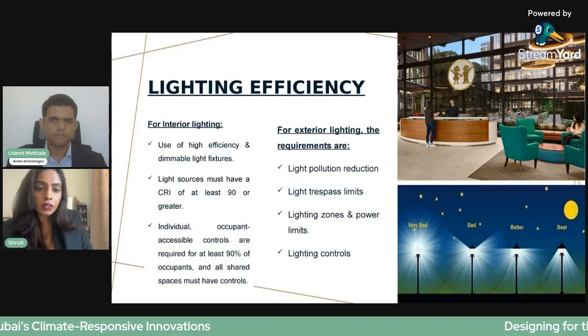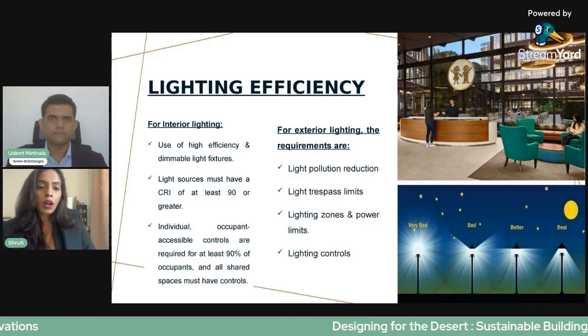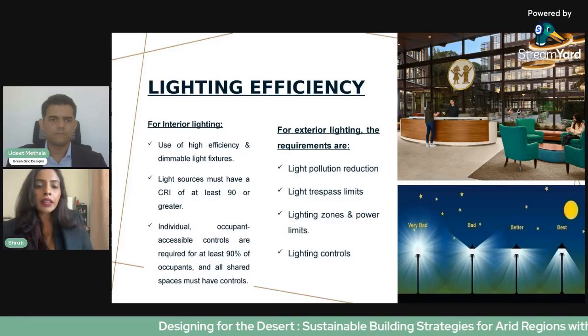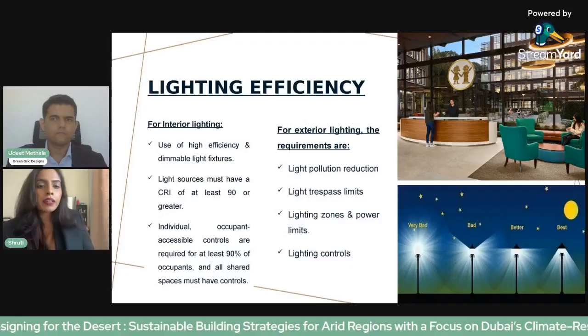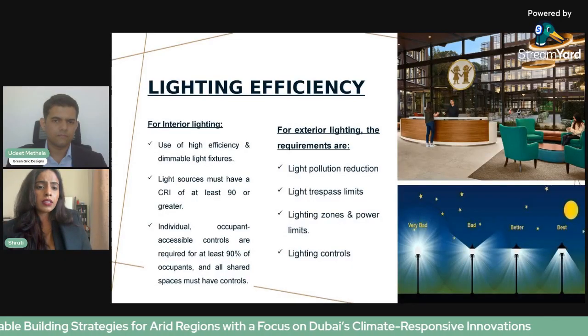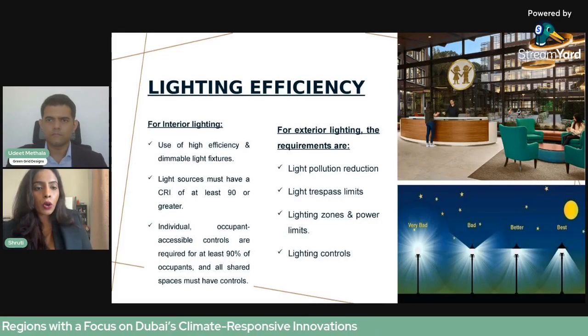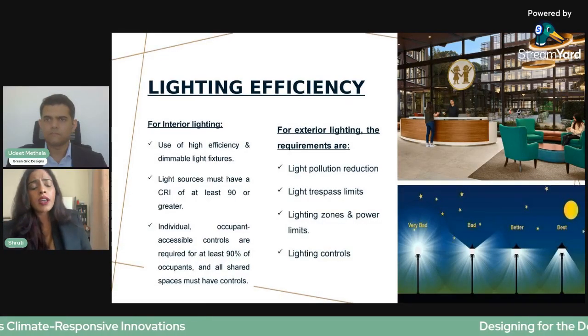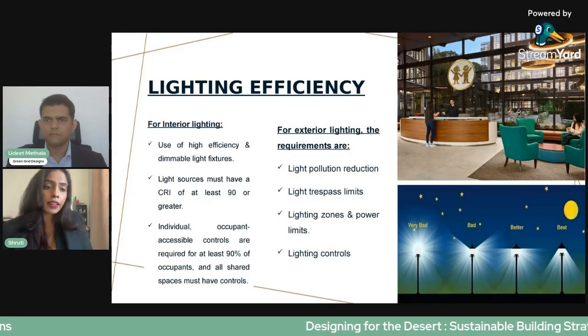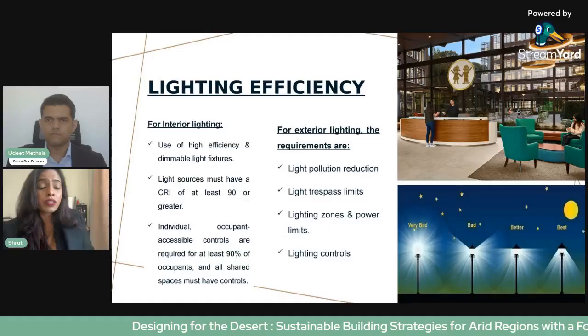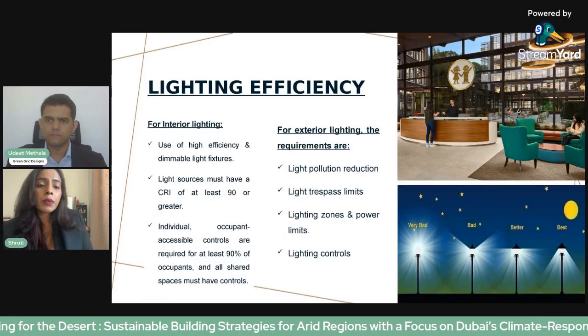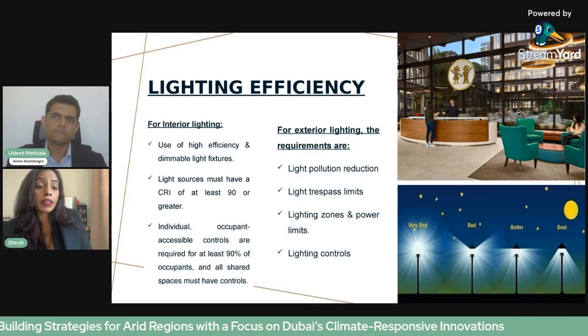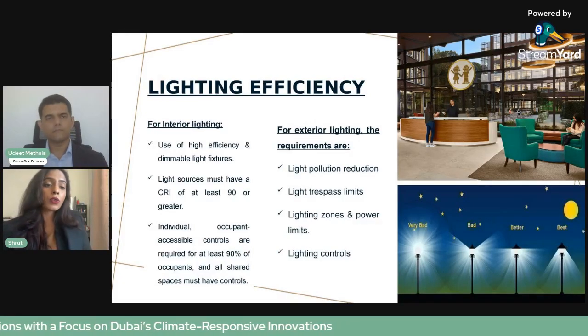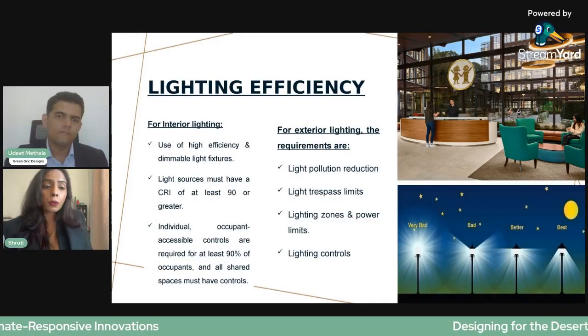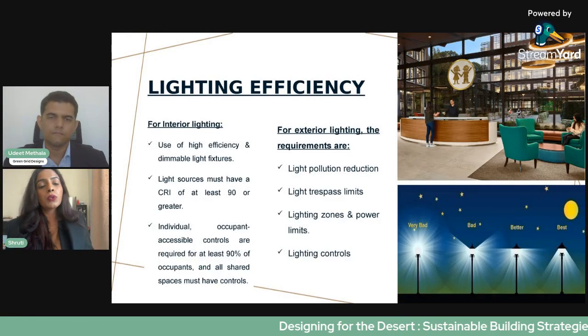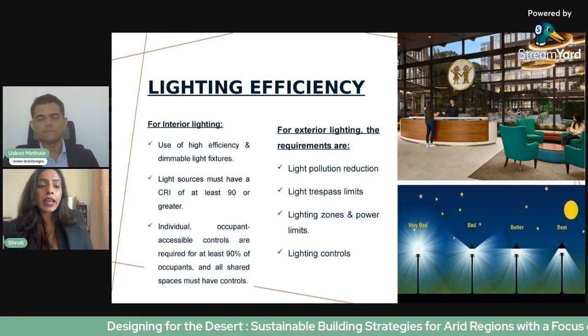Now comes the third category, that is lighting efficiency. In that also we have two categories: interior lighting as well as exterior lighting. Interior lighting is a bit easy to understand: use LED fixtures, give priority to LED fixtures, and use light sources which have a high CRI. CRI is the color rendering index, which shows a clear picture of any object. As per green building requirements, if the value is more than 90, then it is well and good. Also provide occupancy sensors for individual occupant spaces as well as multi-occupant spaces, so that also helps to have better lighting efficiency.